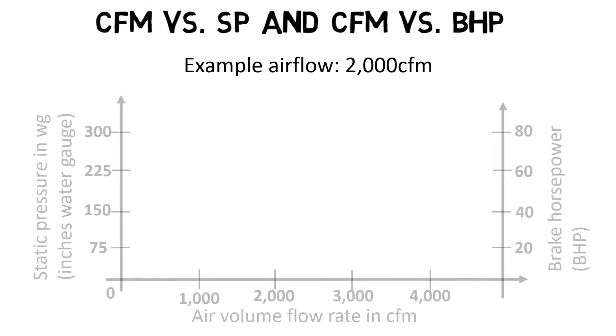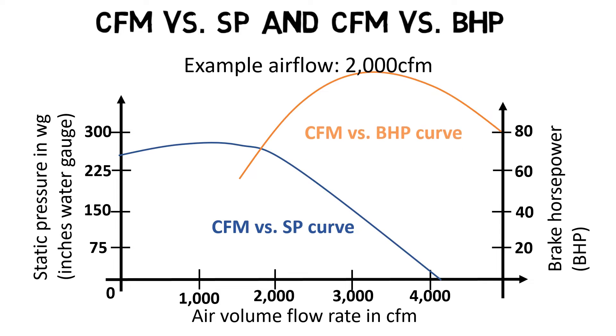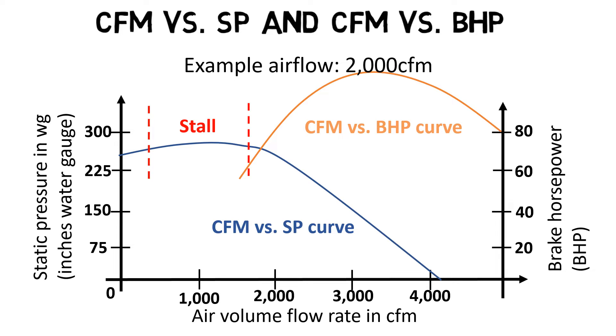The blower diagram usually consists of two curves: the CFM versus SP curve, showing the relation between static pressure and air volume flow rate; and the CFM versus BHP curve, showing the relation between the fan's air volume flow rate and the brake horsepower. A typical blower used in wastewater treatment is a direct drive, centrifugal type blower. The flat section is called the stall region, which is the range where the blower is unstable and should not be operated.